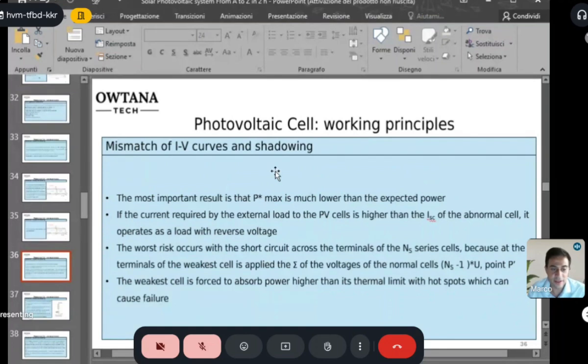So the most important result is that Pmax is much lower than expected. If the current required by the external load from the PV cells is higher than the short circuit current of the abnormal cell, it operates as a load with reverse voltage. This is the worst scenario.